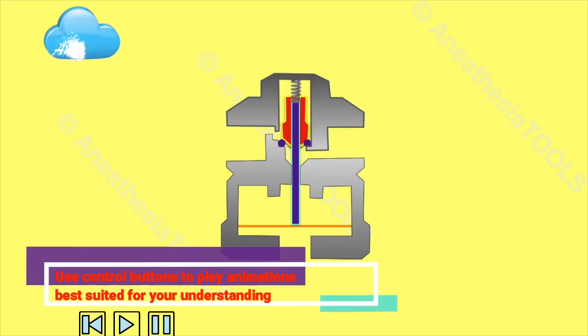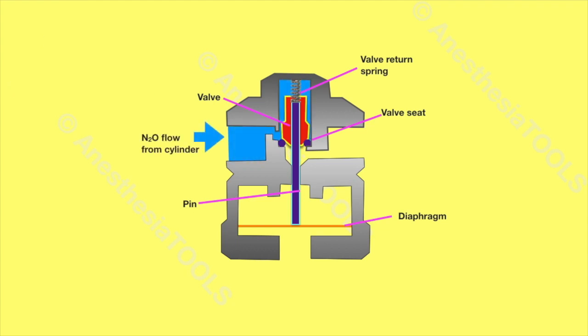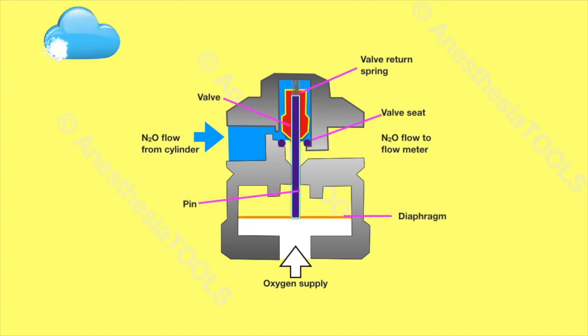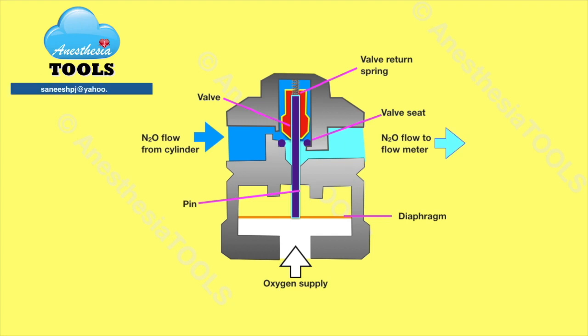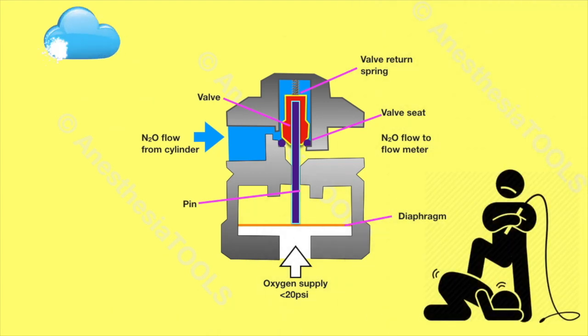This is a simplified internal structure — you can identify the valve, spring, pin, and diaphragm. Here, nitrous oxide flows in from the cylinder but there is no output to the nitrous oxide flow meter while oxygen supply is absent. When the oxygen line is pressurized, the diaphragm is pushed by oxygen pressure, the valve opens, and nitrous oxide output is seen. When oxygen pressure falls below 20 psi, the valve closes and there is no more nitrous oxide output. Thus, the nitrous oxide regulator acts as a slave regulator to oxygen as the master.